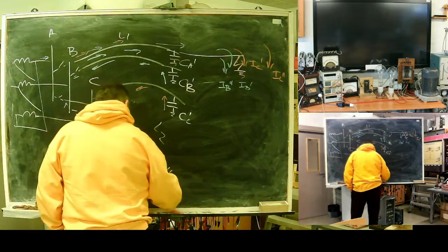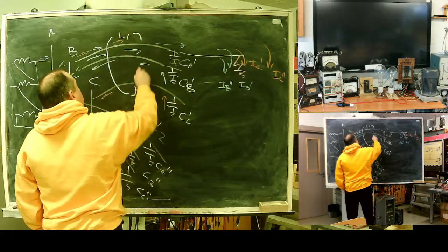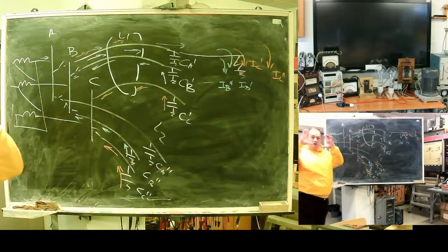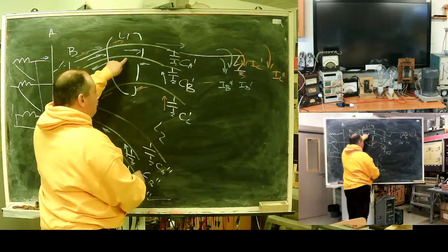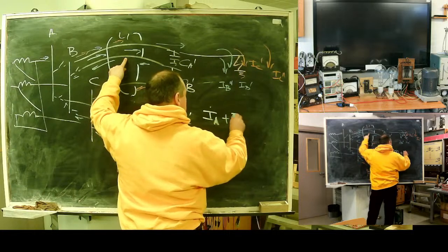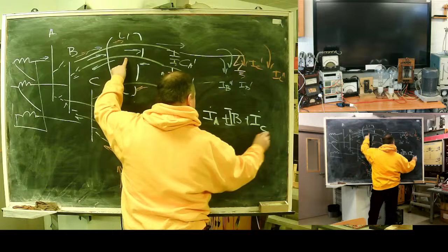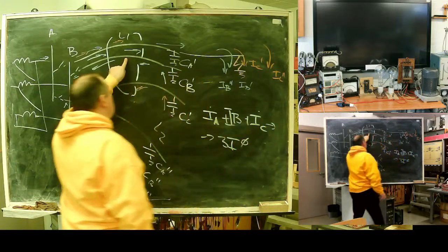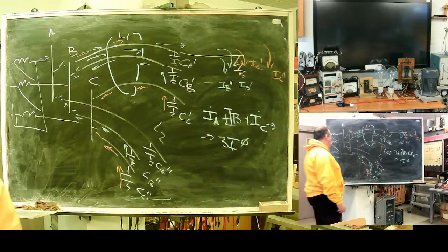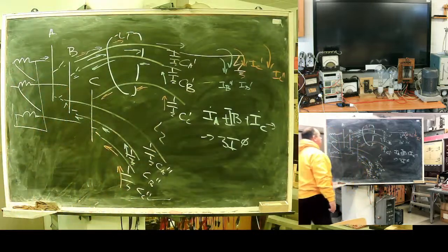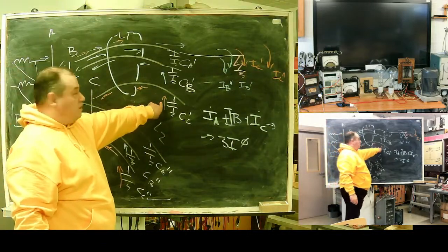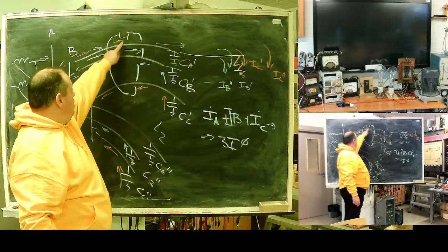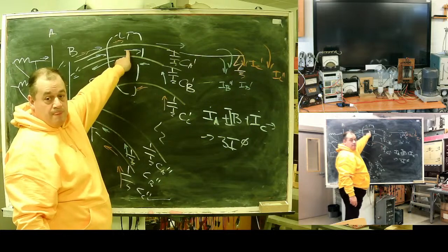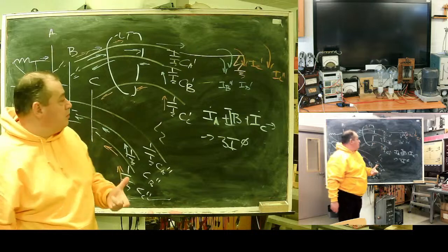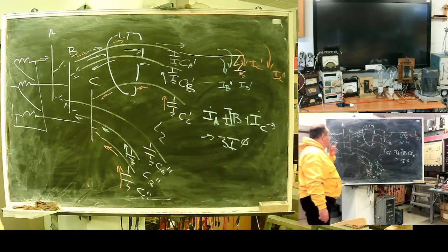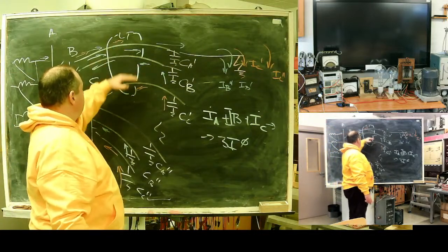And for zero sequence current, I can draw it. Here is my, let's say, contour or loop. Here in my blue ring, I need A phase plus B phase plus C phase. This will give me triple zero sequence current, the only signal I can rely on in this situation. And what does this current contain? Take a look. On orange, on orange. On blue, on blue. My own current appears to go backward, forward. Backward, forward.